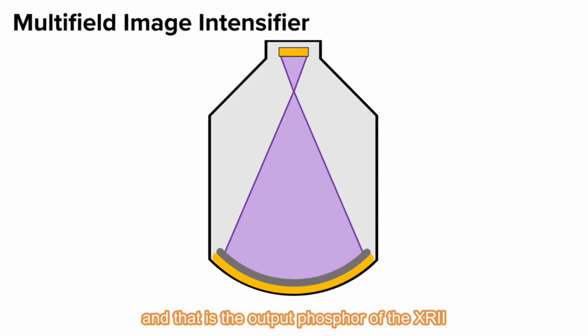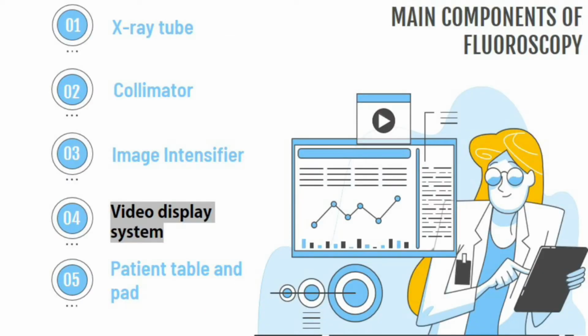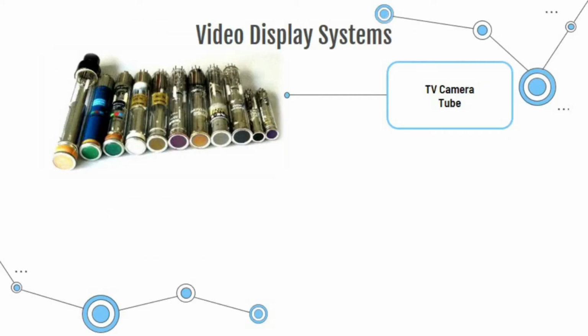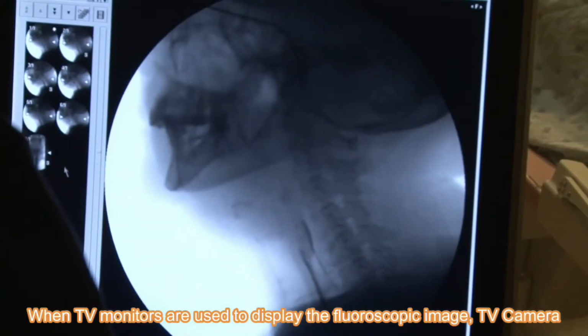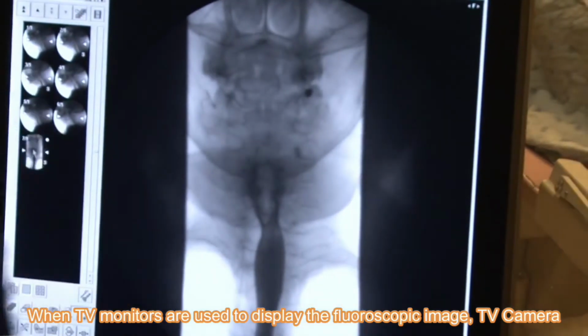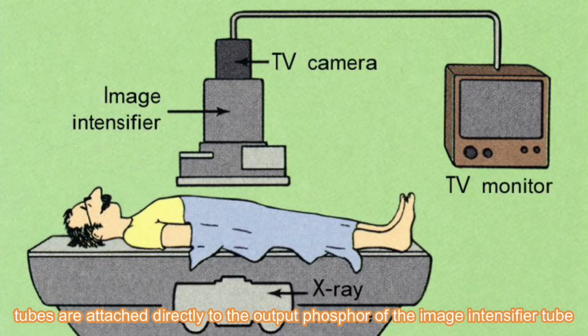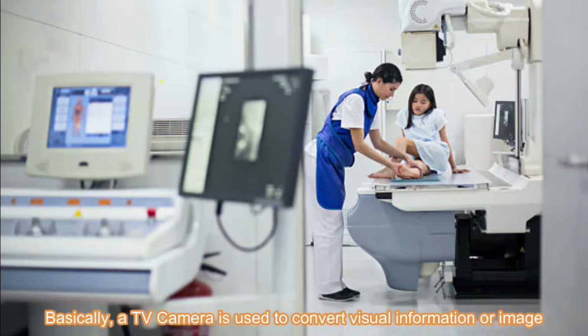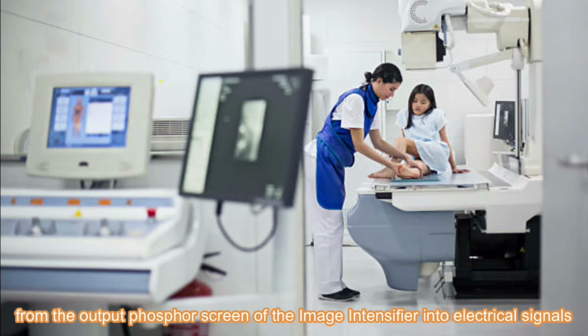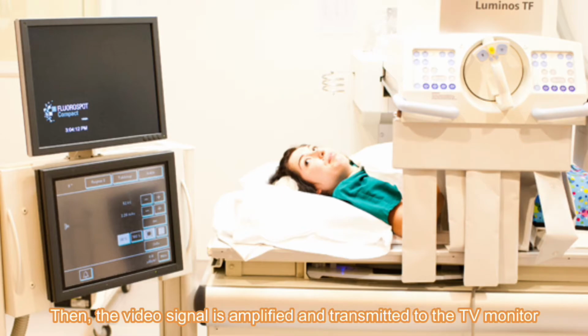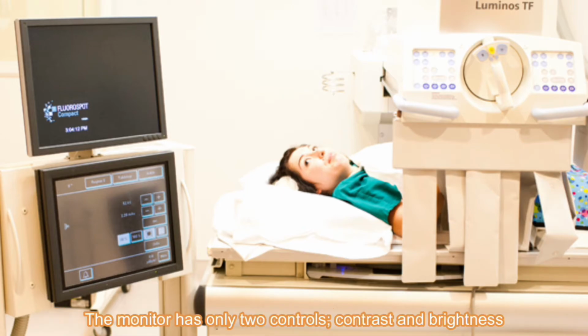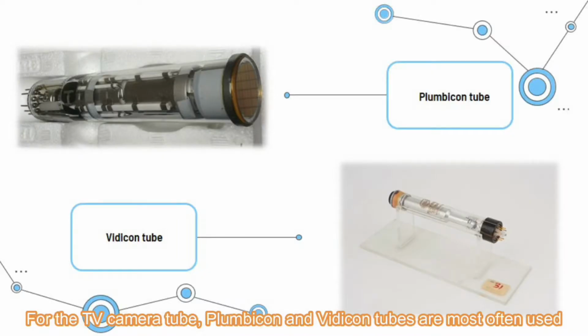the X-ray image intensifier. There are two main components in the video display system, which are the TV camera tube and TV monitor. When TV monitors are used to display the fluoroscopy image, TV camera tubes are attached directly to the output phosphor of the image intensifier tube. Basically, a TV camera is used to convert visual information or image from the output phosphor screen of the image intensifier into electrical signals. Then, the video signal is amplified and transmitted to the TV monitor. The monitor has only two controls, which are contrast and brightness. For the TV camera tube, Plumbicon and Vidicon tubes are most often used.